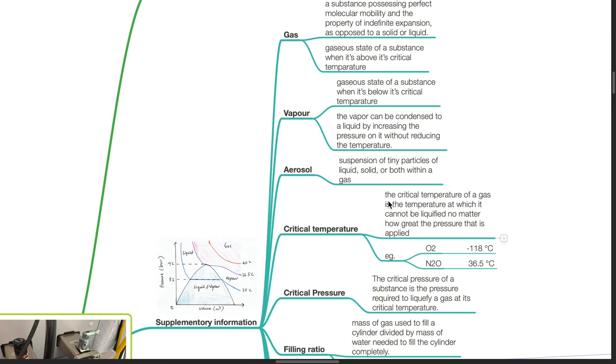Critical temperature of a gas is the temperature at which it cannot be liquefied no matter how great the pressure that is applied. For oxygen, it is negative 118 degrees Celsius. For nitrous oxide, it is 36.5 degrees Celsius.